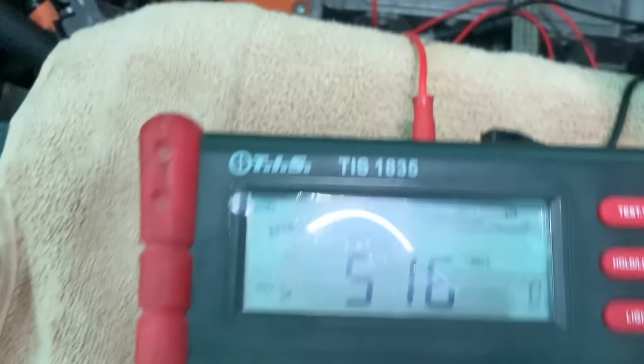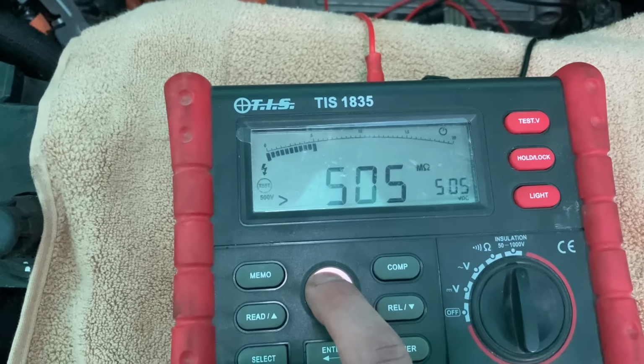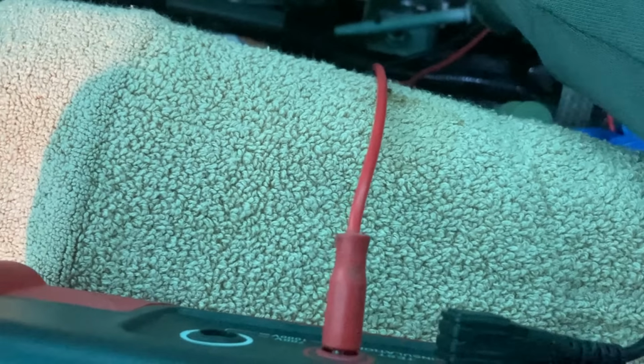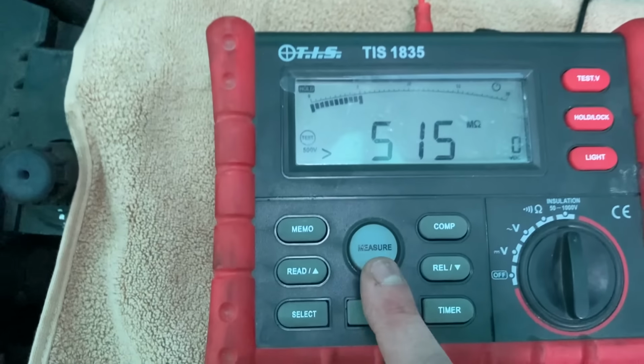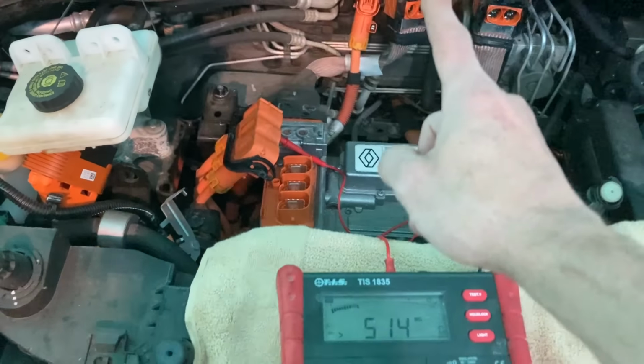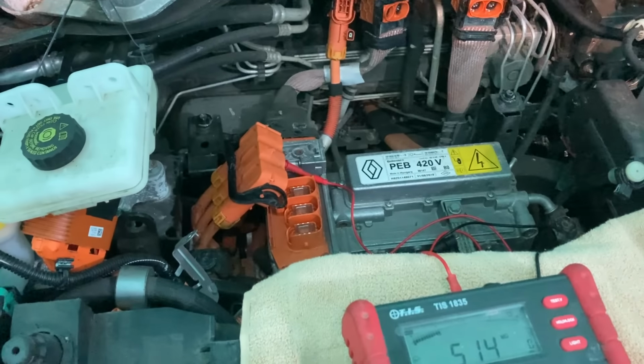So the motor, yeah, it's a pass. These will be a pass basically. These two now, the first two passed, the second two will pass just because of the way it's wired together. Effectively they are coils that are all wired together. So now we've got the four connectors on the motor have all passed.